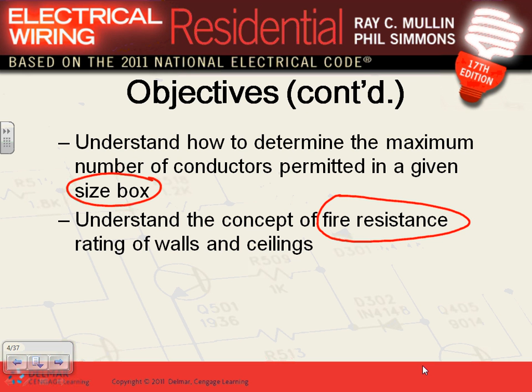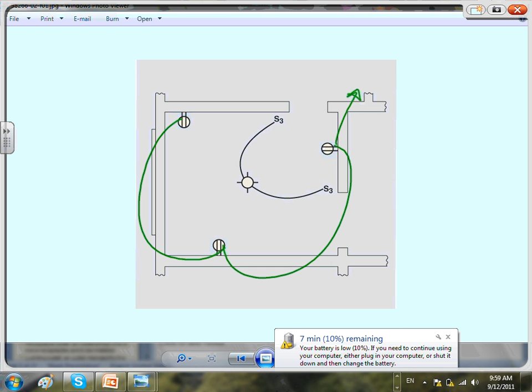Okay, I'm going to switch from the PowerPoint presentation to a couple of slides here, pictures basically. Let's go right here. So this is what you guys are going to be doing with Chad - here's a room, and I need you to put your receptacles in the room and circuit them. That's what symbols are. I have 1, 2, 3 receptacles in one room, and this is exactly what you're going to be doing with me. What you need to do is circuit them - we're going to grab circuit one, circuit, and from here I'm going to go with a home run. This is going to be circuit number 1 from apartment panel 1.